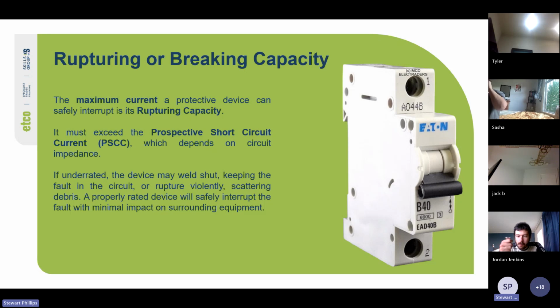One thing to ask your tradesman about, if you're working residential or commercial, is that there is actually a part of the wiring rules that says we have to protect against the ingress or egress of fire in the switchboard by maintaining a closed opening. Basically, if you can fit your finger through the hole, you need to seal it. So when you install domestic boards, you don't break out every single punch out in the board. You only bring in the ones you need to, and if the holes are too big, you need to seal them. I've got about 20 tubes of intumescent fire sealant at home. Even though it says it's expired, that stuff doesn't go off. I've asked fire engineers, that stuff doesn't go off.